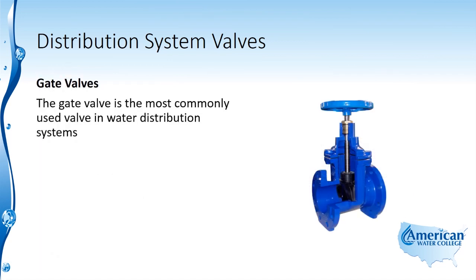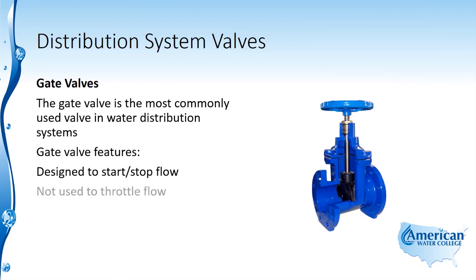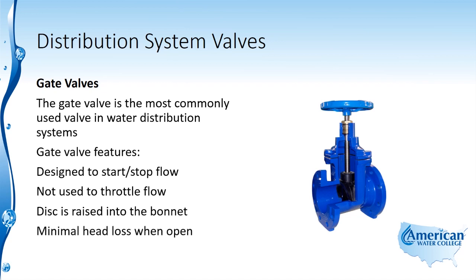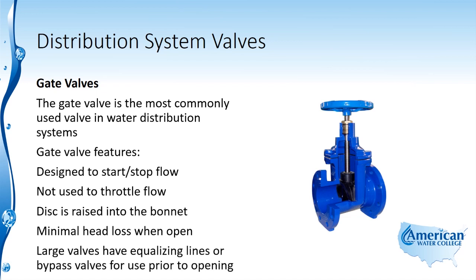The gate valve is the most commonly used valve in water distribution systems. They are designed to start and stop flow and are not used to throttle flow. The disc is raised into the bonnet and there is minimal head loss when the valve is open. Large gate valves have equalizing lines or bypass valves for use prior to opening so that the gate is not damaged.